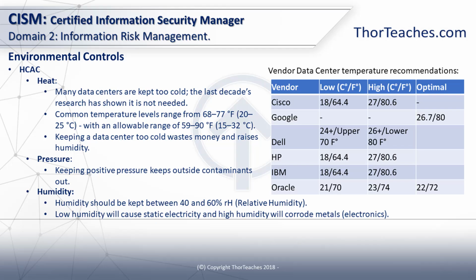So over the last 5 or 10 years, it has become common knowledge that it's okay to raise the temperature in a data center. As you can see in the charts from the vendors where they recommend their equipment be used, there's definitely some disagreement on what the optimal temperature is. And some vendors have very wide ranges of where the equipment is going to work well. Somewhere in the low 20s for Celsius or in the low 70s for Fahrenheit is probably a good range to shoot for.